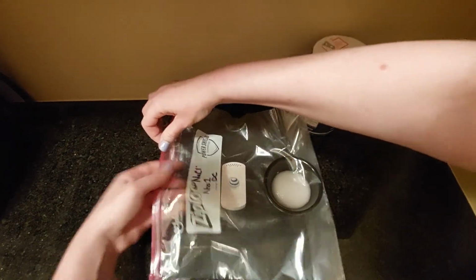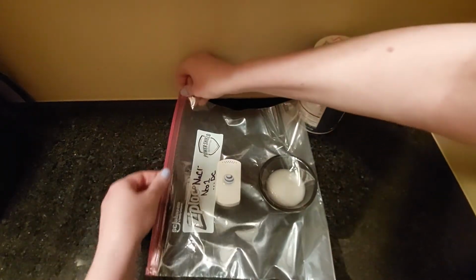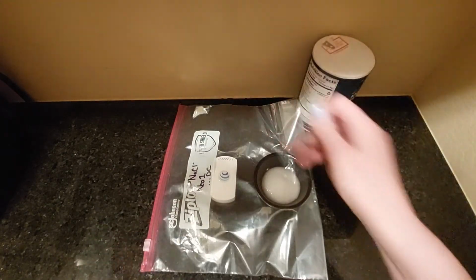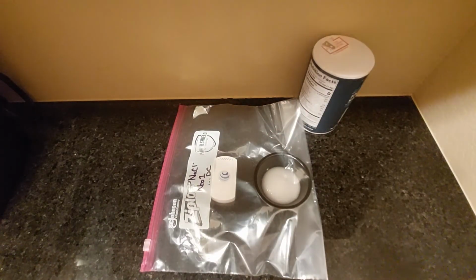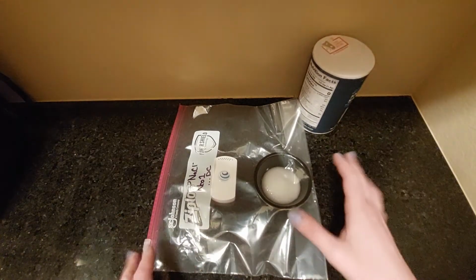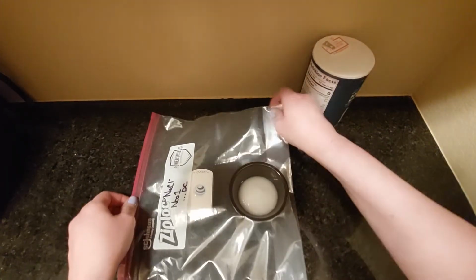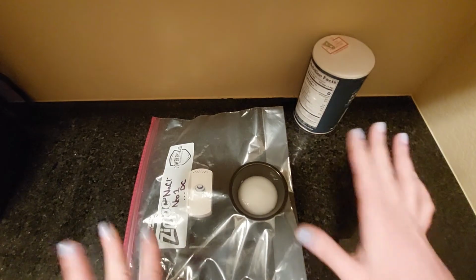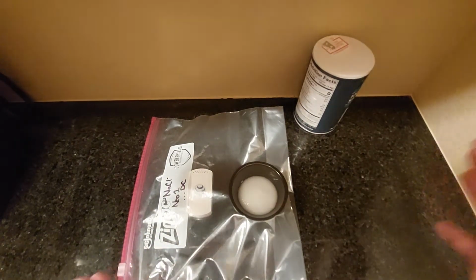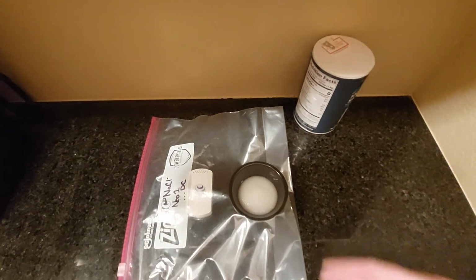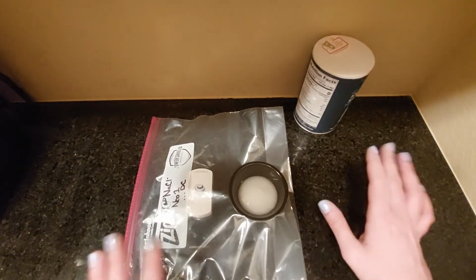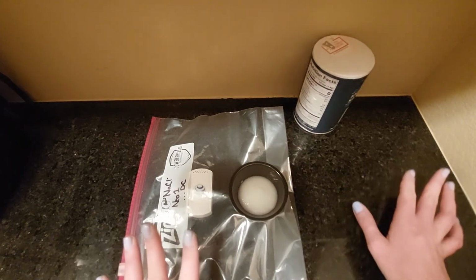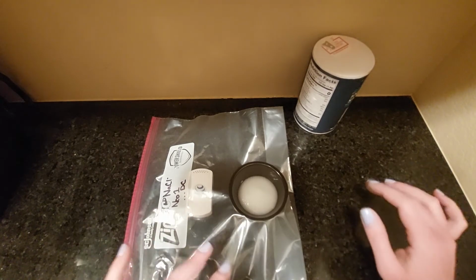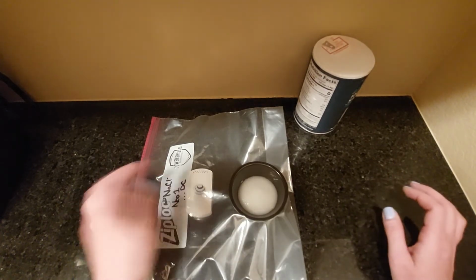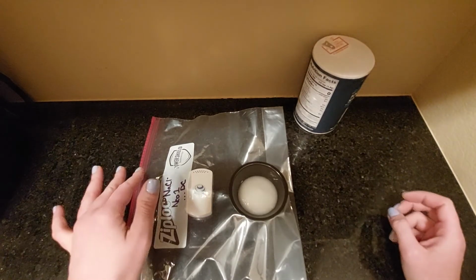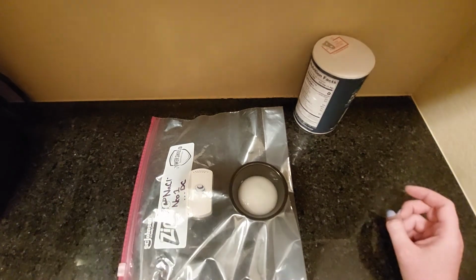Now we're going to set this in there. We always want to do these tests in an area where we have fairly stable temperature and humidity. Even though we're in a closed container, you don't need to worry about pressing all the air out. Just go ahead and set it in there. Give it at least like 4 hours or so. Some people like to do it for 24 hours. That's not really necessary in this case. Just give it a few hours, and then we'll go ahead and reset this, take the readings, and then readjust our calibration in the app.